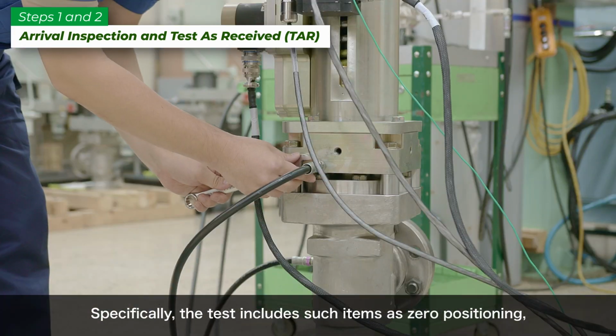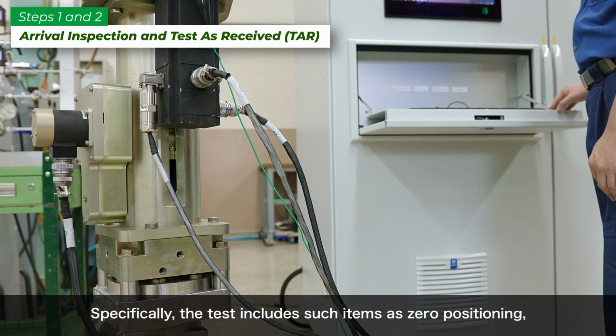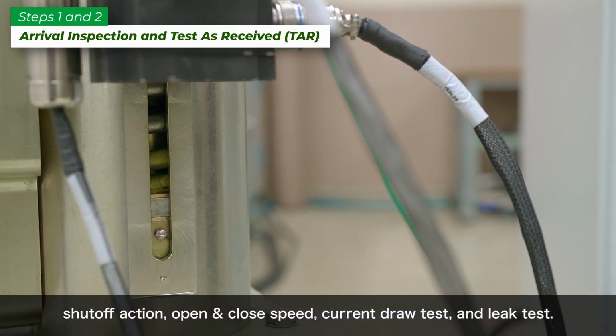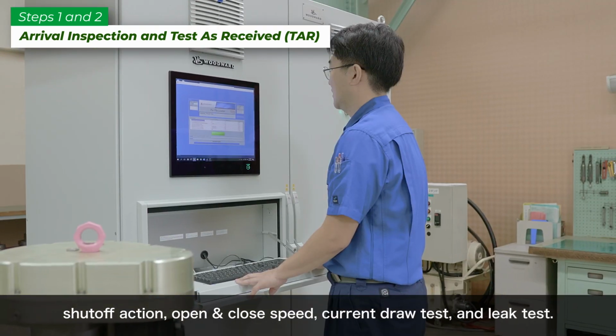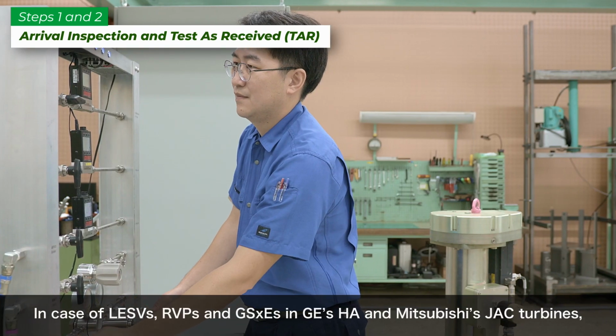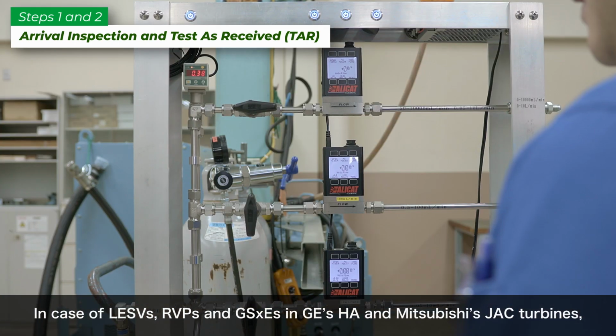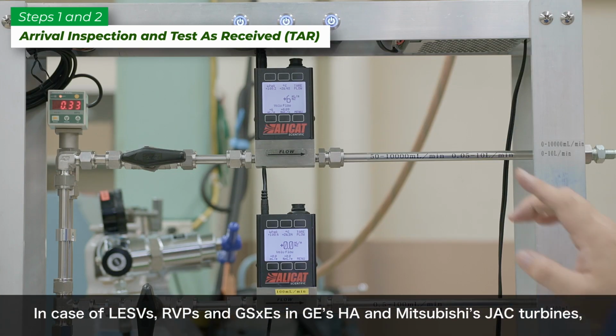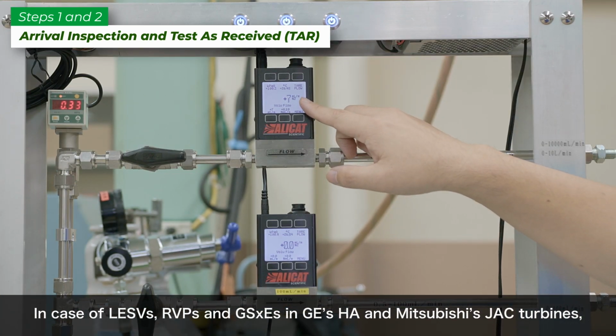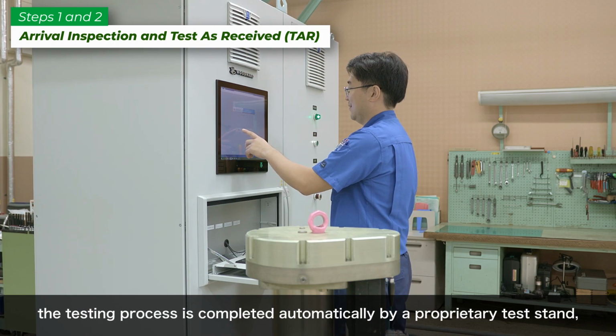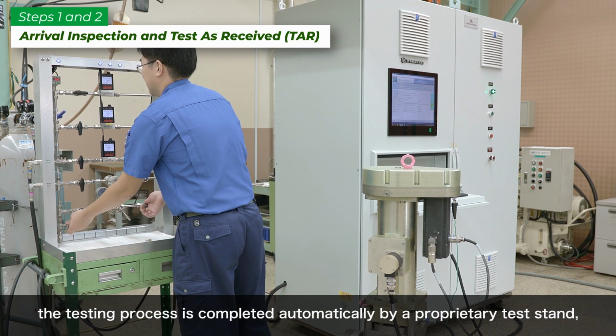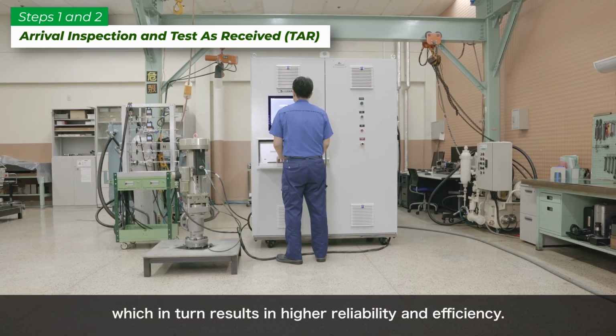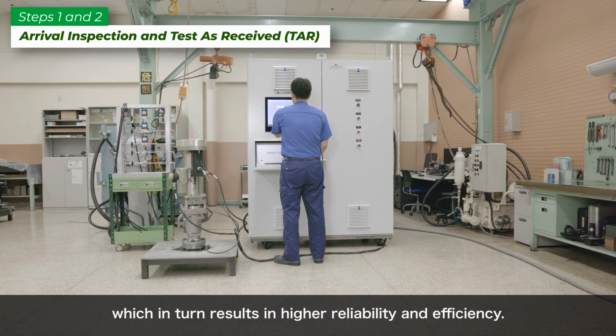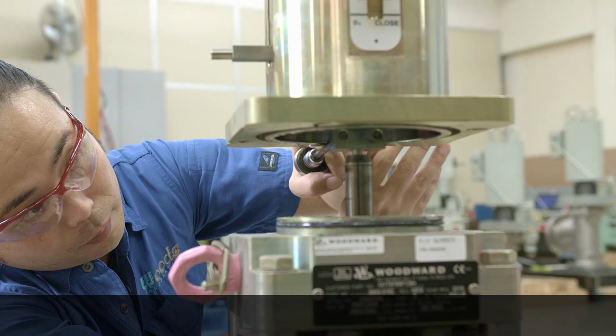Specifically, the test includes such items as zero positioning, shut-off action, open and close speed, current draw test, and leak test. In case of LESVs, RVPs, and GSxEs in GE's HA and Mitsubishi's JAC turbines, the testing process is completed automatically by a proprietary test stand, resulting in higher reliability and efficiency.